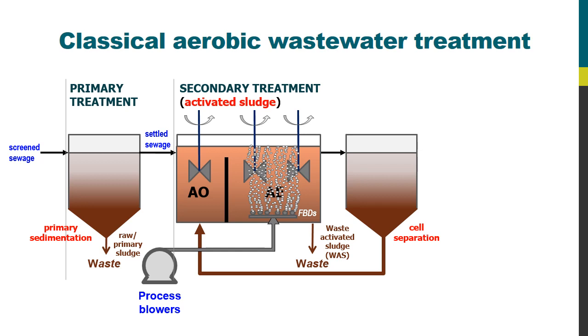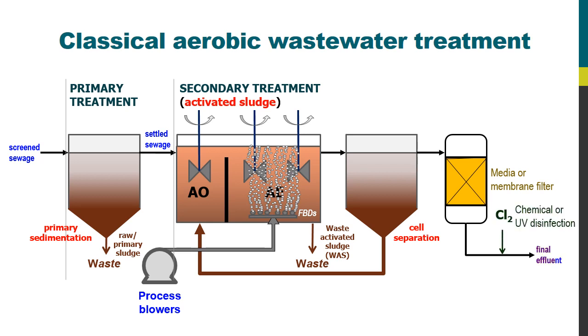But if you want something a little bit more than that in terms of your treated water quality, then you have to add a tertiary treatment stage, which normally comprises some kind of solid-liquid separation process, which would be either a media or membrane filter, followed by some kind of disinfection process, either chlorine or perhaps UV disinfection, to give you that final effluent.